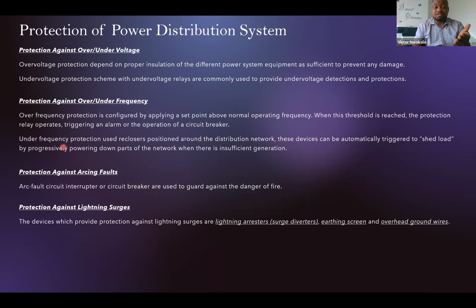That we protect against frequency, under frequency there, and use things like recloser to cut off a section of the supply and let load shedding take place in order to balance the load. Lightning surge and arcing faults, these are also common in power distribution, and they are protected using interrupters, circuit breakers, and specially designed protection relays.